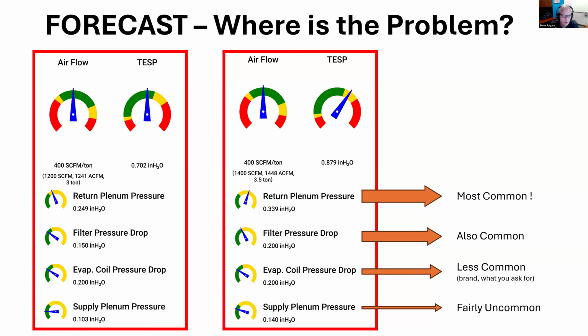So that's a fairly new tool. It's about 5 years old that we've been selling the TrueFlow that has the app to back it up. So that's what I can tell you about the TrueFlow and how it can help with the retrofit process, making sure that the duct capacity is capable of moving the airflow that is needed for the system. So what airflow is needed for the system, that's doing your Manual J load calculation and Manual S selection to find out what system you need. Then you'll know, and then you can evaluate the duct system for that capacity.